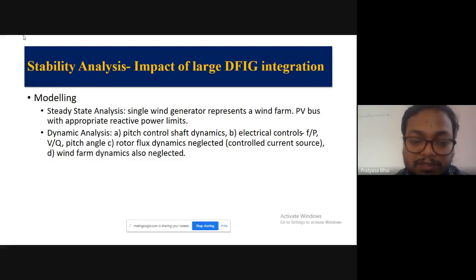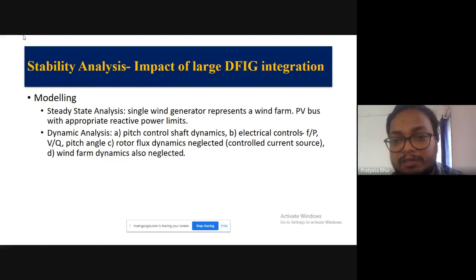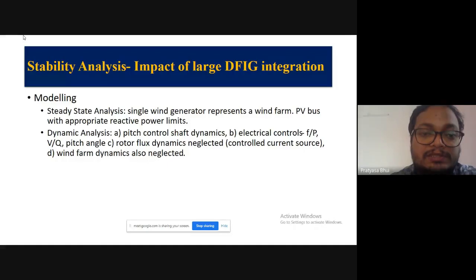connection diagram, the circuit diagram for the DFIG. It's basically an induction machine. The rotor is also connected to the grid with two back-to-back converters. So the rotor side converter will control the rotor current very fast. So the dynamics associated with the rotor current or the rotor flux will be neglected. So we can assume it as a controlled current source. And wind farm dynamics is also neglected. In a wind farm, you may have hundreds of generators. Now we'll assume that their dynamics is similar. So there is no dynamics in between generators in a farm. So we'll consider only a single generator for a wind farm.